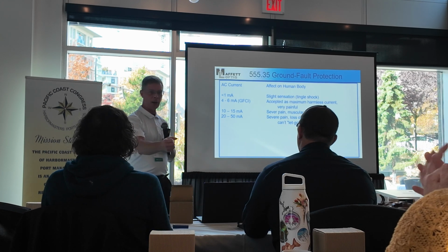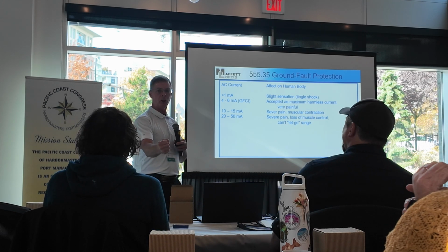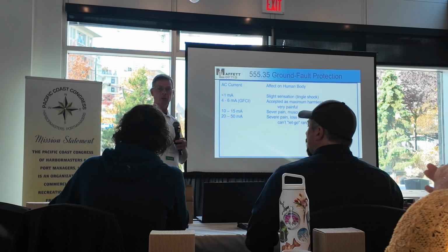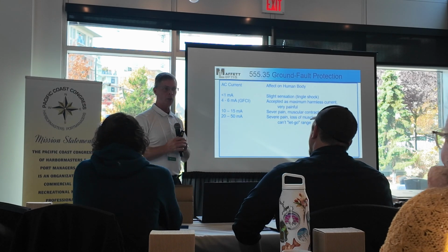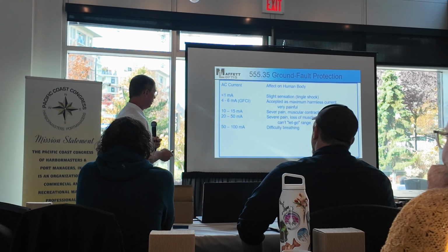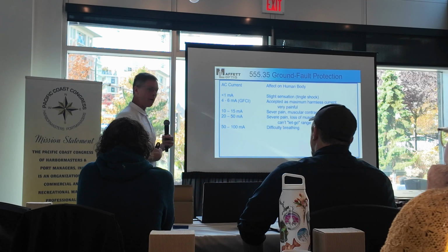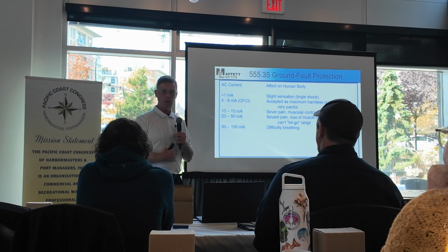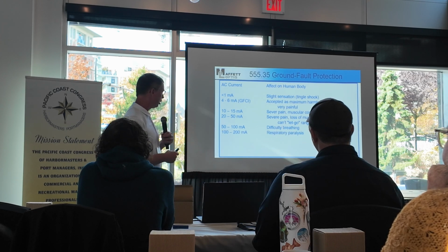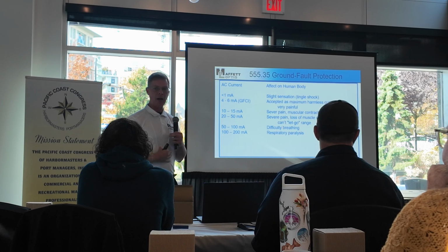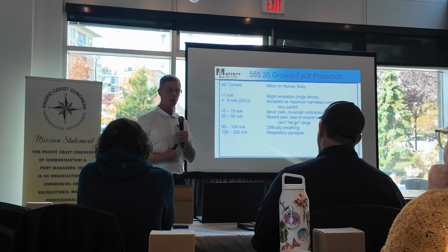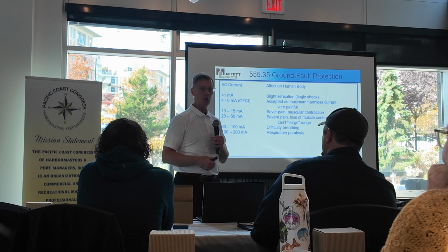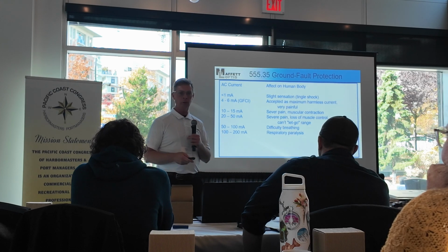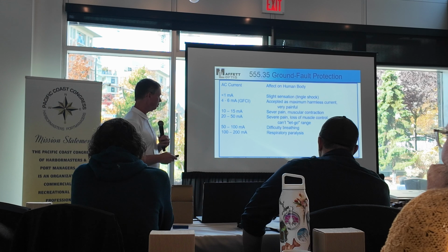Have you ever heard that? You grab something and you can't let go because it's too much current. Your muscles freeze up. That's what that is, and that's what causes electric shock drownings. Up around 50, your diaphragm starts having issues, and especially above that, up to 100 milliamps, is total paralysis of your diaphragm. That's electrocution. That's where enough electrical current is flowing through your body that it's affecting your organs and physically electrocuting you.